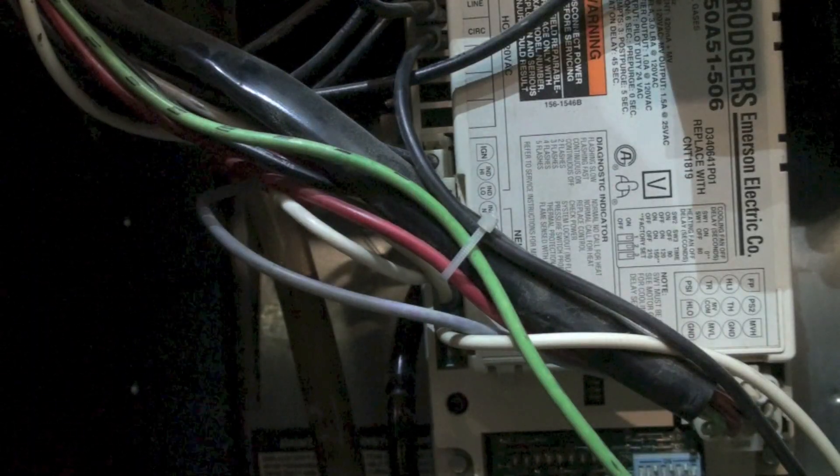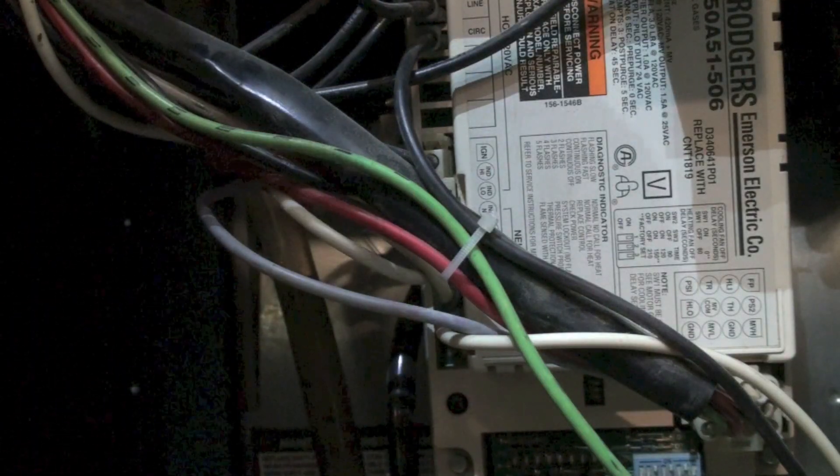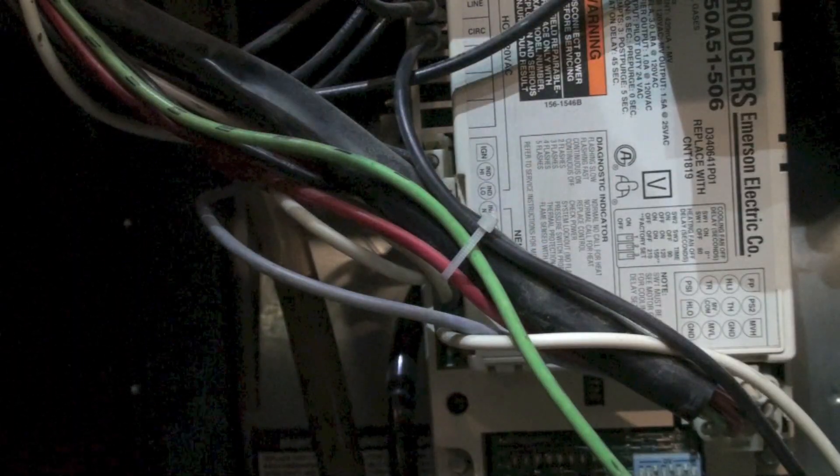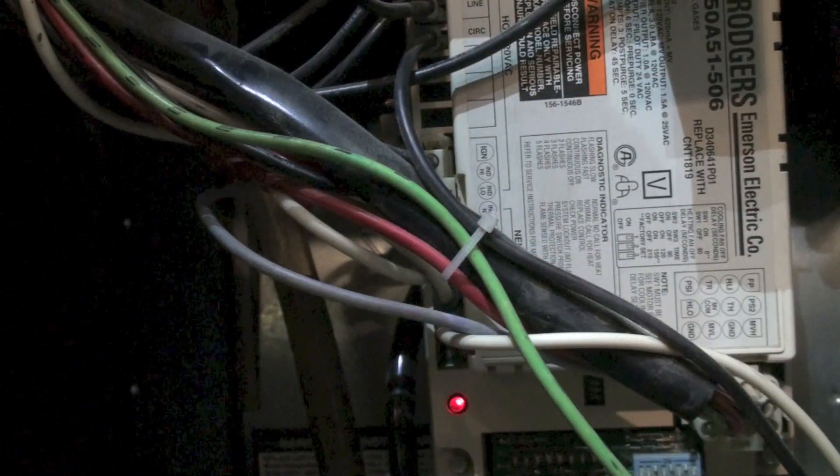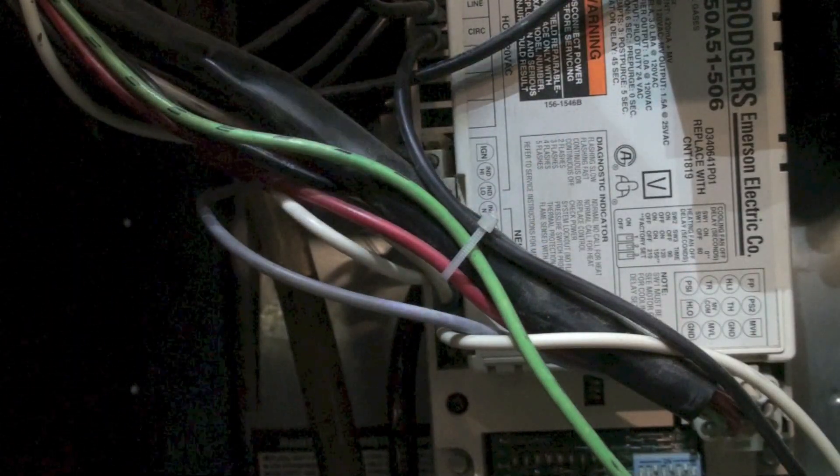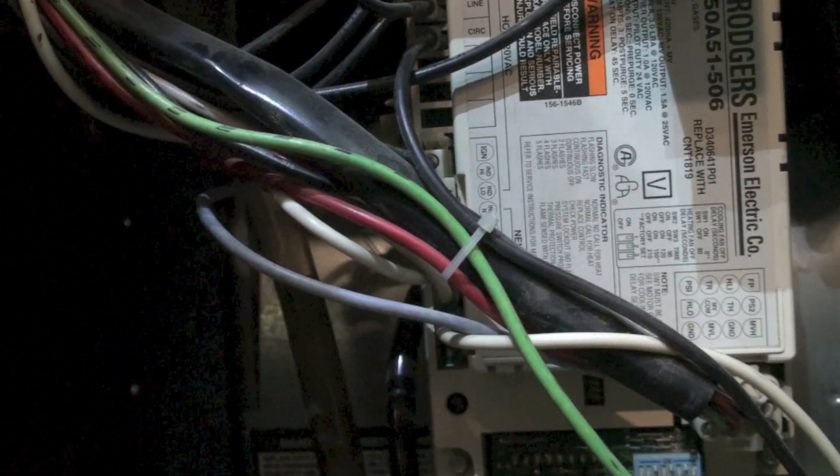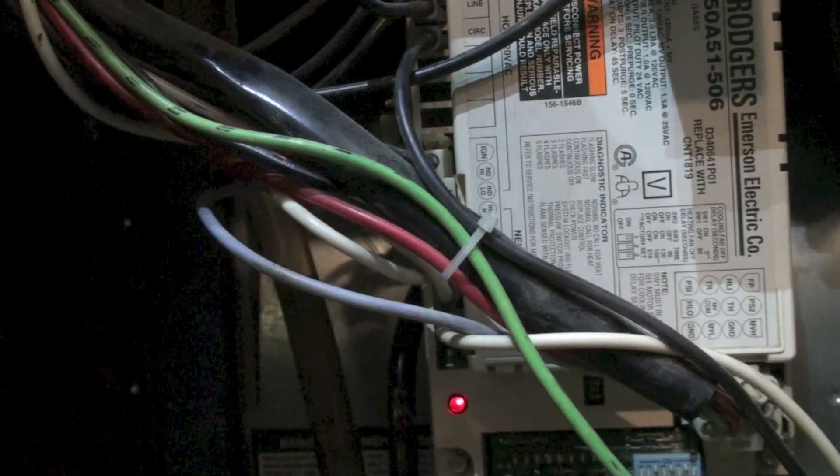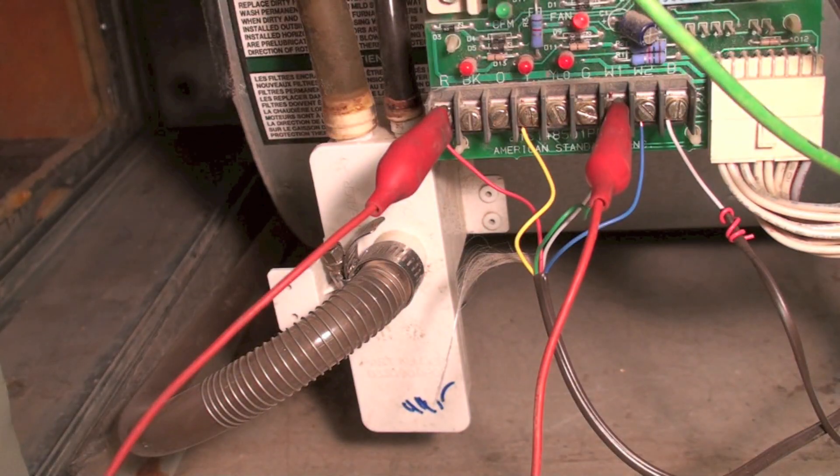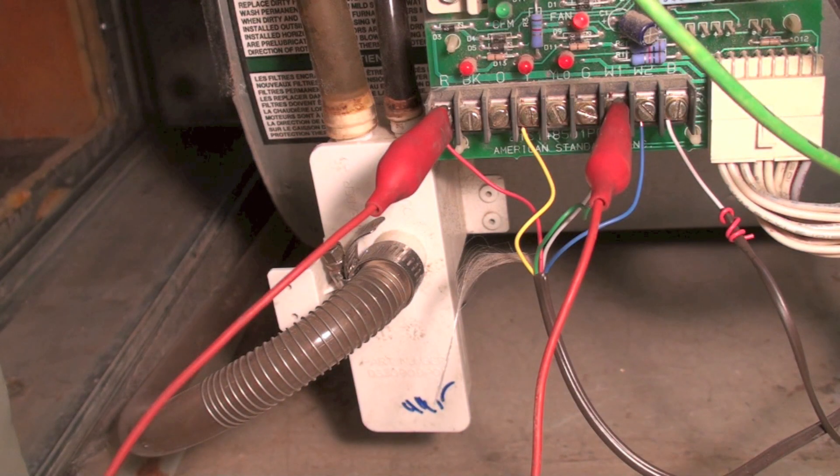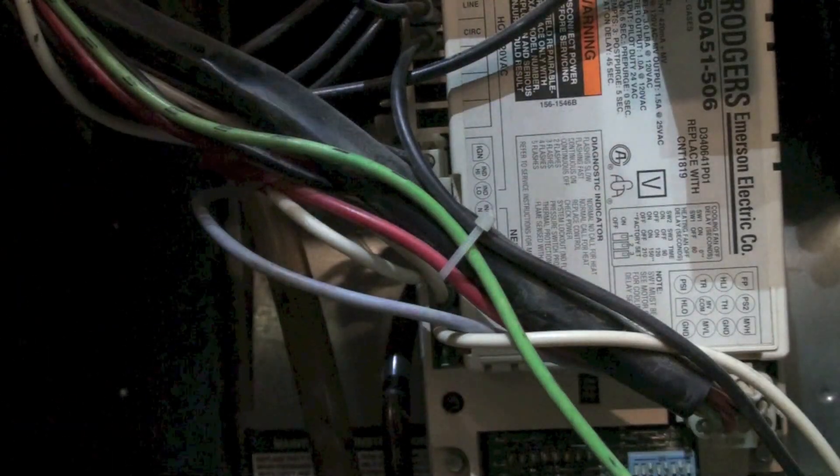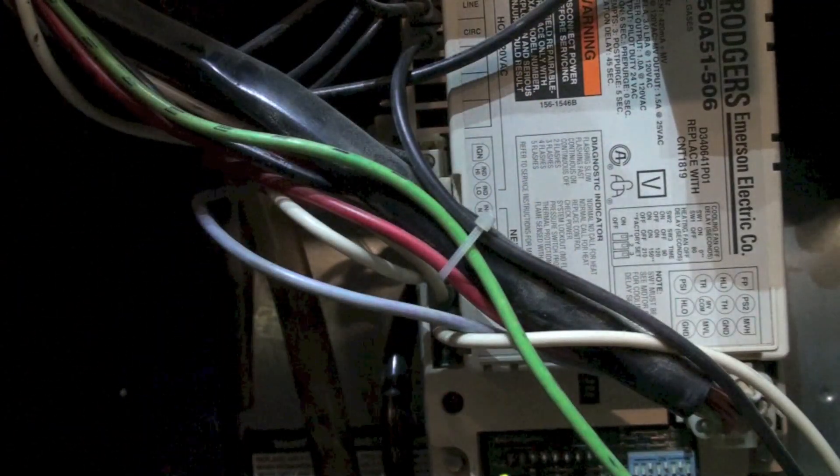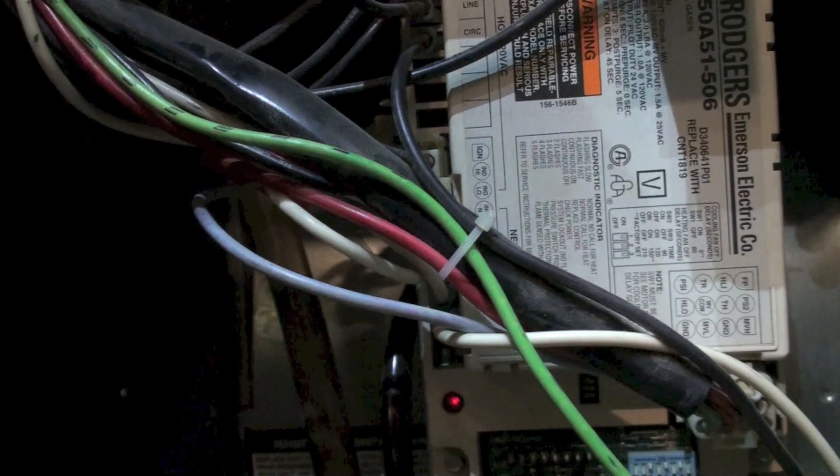The other thing that happens here commonly is the condensate drain, which comes on the bottom of the inducer. On this furnace it's right there. Sometimes that drain will plug and that will cause a problem. Usually you hear a noise in the inducer from it. So that's a pressure switch problem.